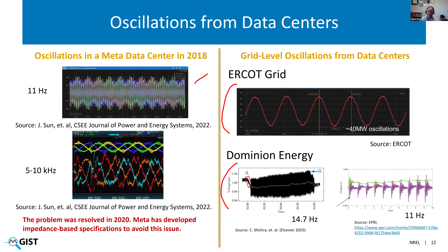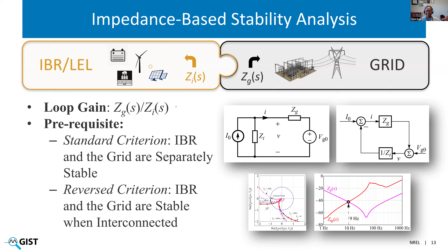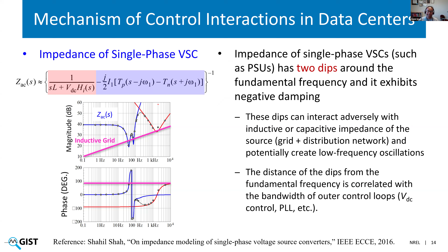What really was the core of the problem was that the PSUs were interacting with the grid, and we need to look at the broadband impedance response, or frequency domain impedance response, to understand how the data center building was interacting with the PSU. I'll probably skip this slide, which just shows how we can have subsynchronous oscillations because of interactions between all the IT racks and the grid. This is similar to what we see with IBRs. The problem is, again, negative damping because of active controls within this frequency range. But in the interest of time, let me quickly cover the specifications from Meta.